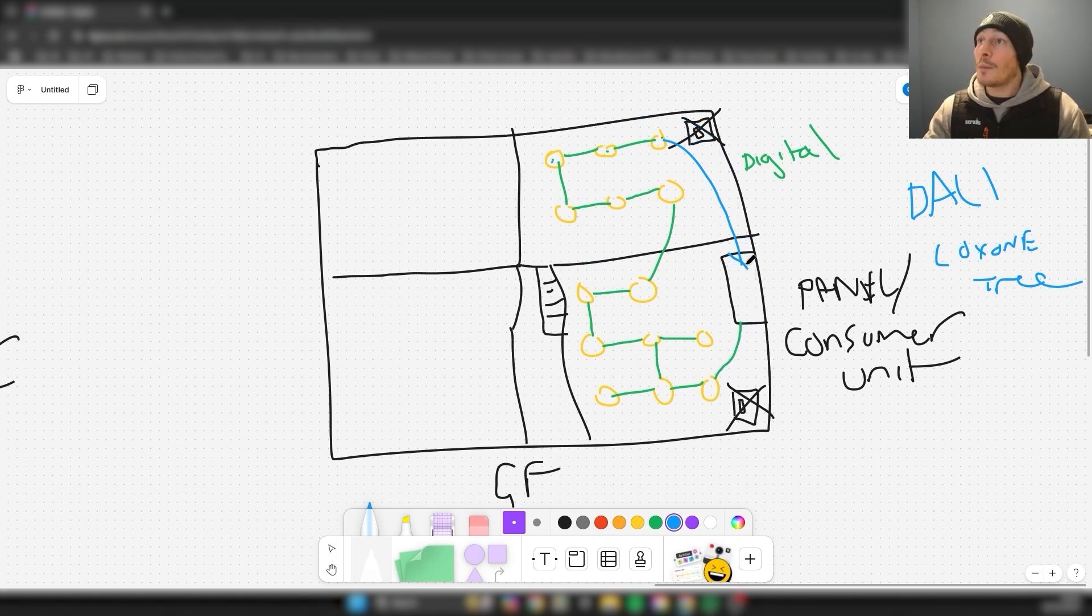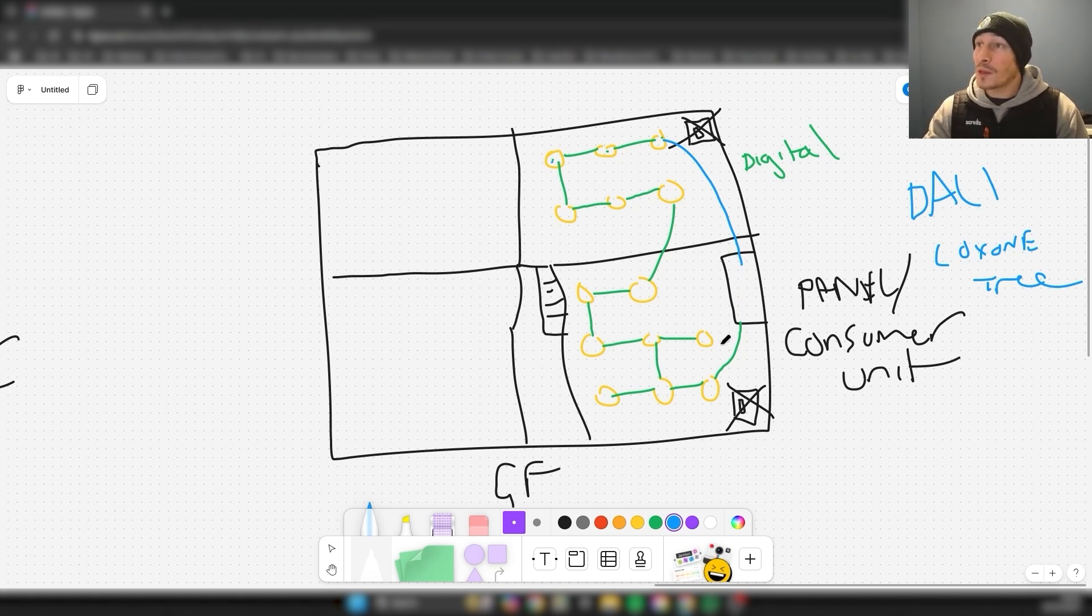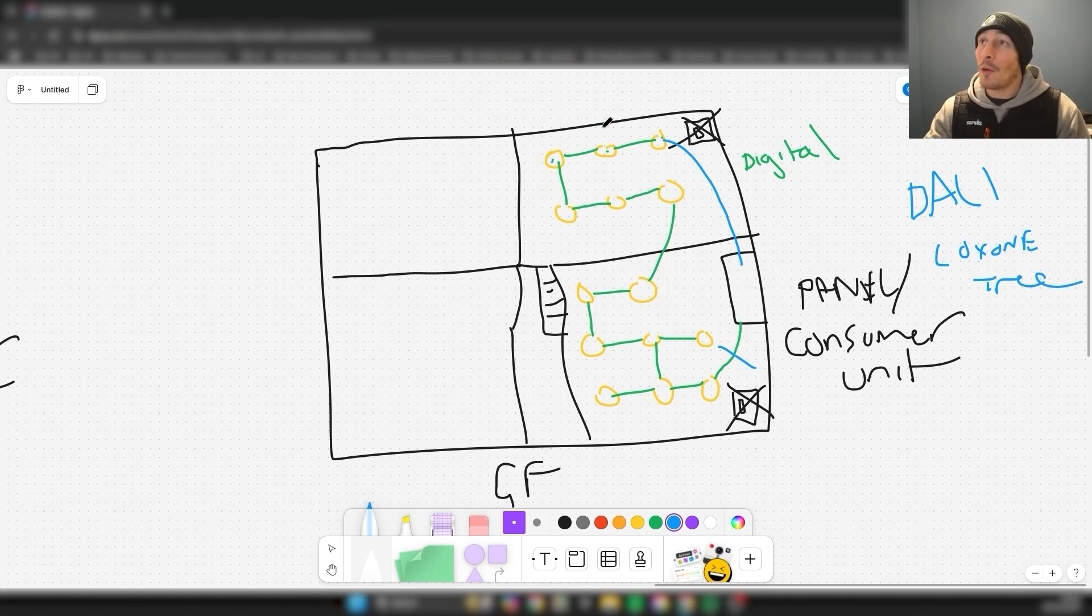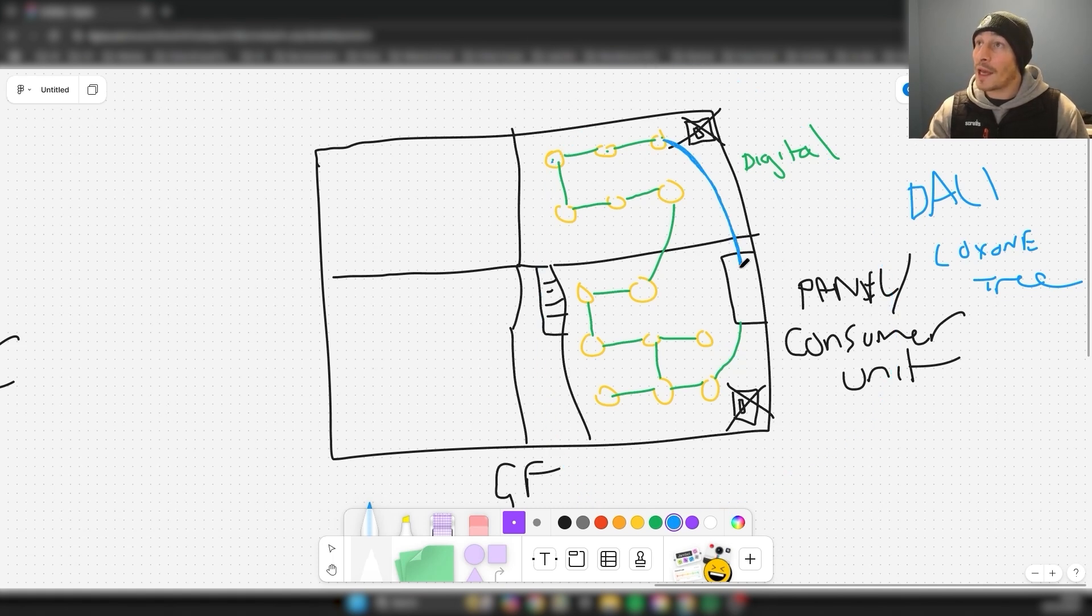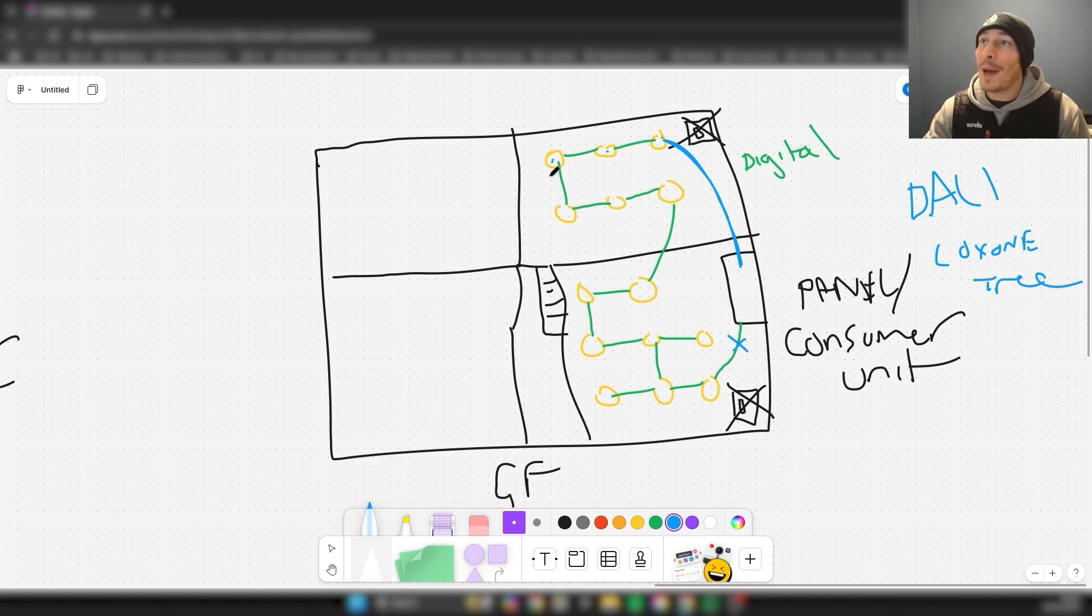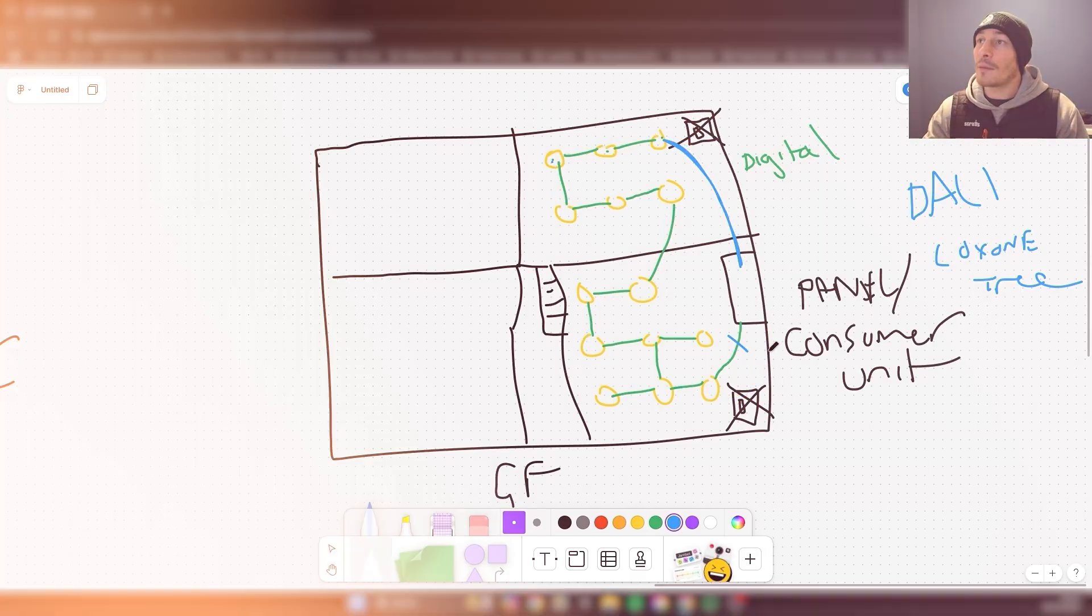I would have it there just for redundancy. So let's say that someone put a screw through this cable in the wall or ceiling and we weren't able to connect to all of these lights, we've got this cable here as a redundancy measure so we can then connect and program and get power to all of these lights moving this way instead.